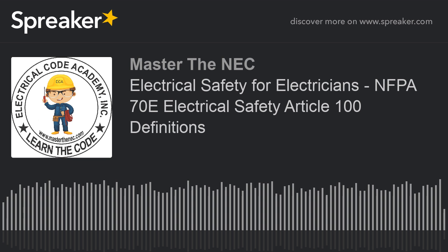A great example of this would be a doorbell circuit, okay? Secondary side of a doorbell transformer, 24 volts, 18 volts, 12 volts, whatever it may be, whatever your flavor. That is not an electrical hazard. Okay? Now, with that said, could you still get a light shock from it if you're on a ladder and it startles somebody? Maybe. But again, as far as NFPA 70E is concerned, it is not an electrical hazard.